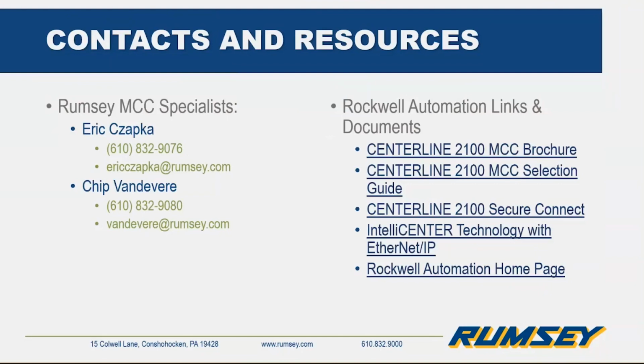All righty. Yeah, well, the horizontal bus is one continuous bus throughout the MCC. So other than the isolation between the sections, which are full metal plates going back and forth, up and down in the vertical, there is protection between sections. As far as the vertical bus goes, you saw that Bakelite red plastic material that goes the total length in the back of the MCC, isolating that from the front. And also Eric touched on our different options for the shutters. We have no option, just a hole for the shutter. You can get plastic caps to go over those shutters, or the automatic shutters, which will withdraw when you enter a bucket. We can get you more information on that, but does that basically answer the question?